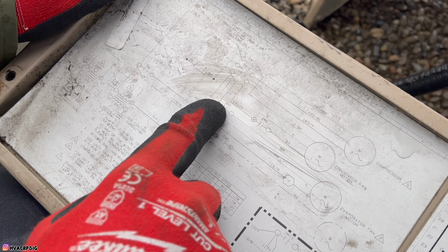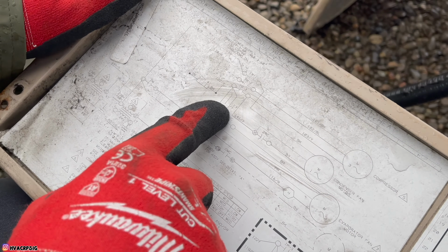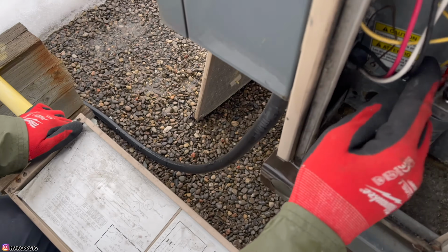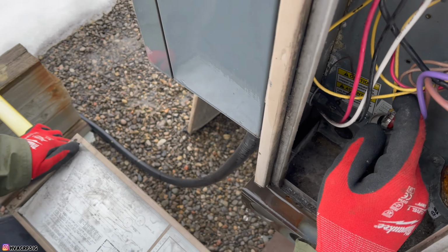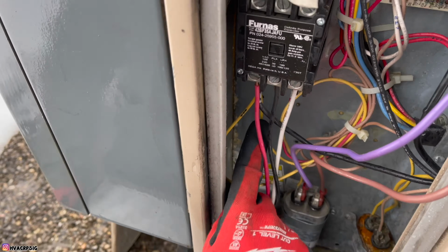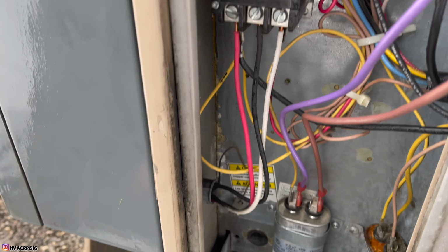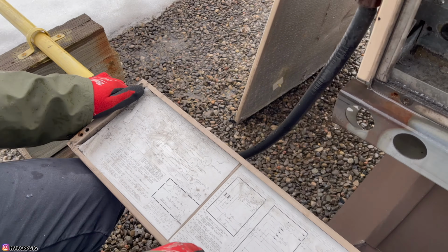The purple goes to the other side, and the same side as that 123 yellow wire, which is this little guy here, which goes back on the line side of the compressor contactor, which is also where the main power is. Because it's 208 single phase, that's how we're getting our two line sides.